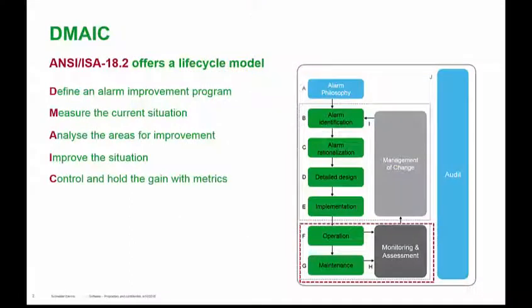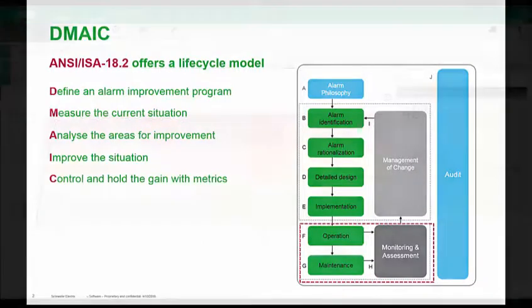One of the things we talked about at the beginning of this video was the ISA 18.2 guidelines — one of the things they discuss is the ability to measure the current situation, analyze the areas for improvement, and improve the situation. One of the ways we do that is with a tool called Alarm Advisor, which allows you to go back in time and look at the alarms to understand where they are coming from. Let's take a look at the Alarm Advisor.